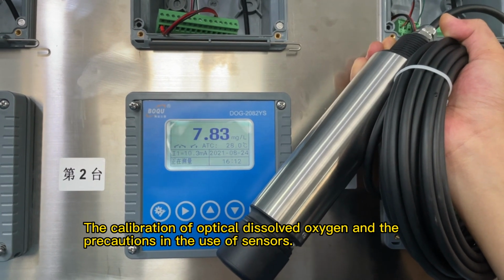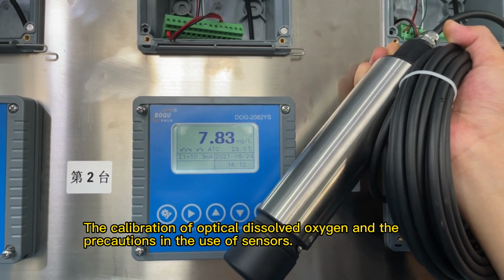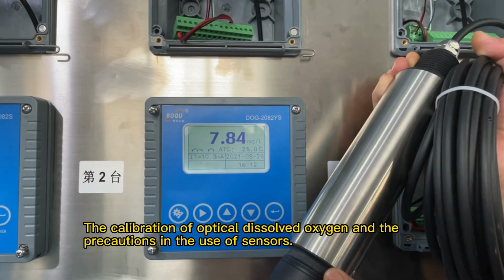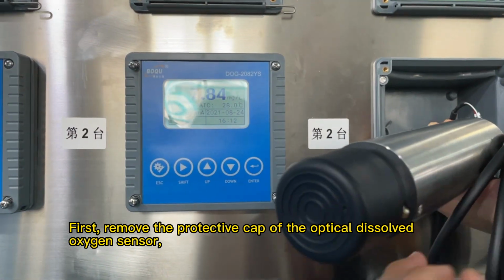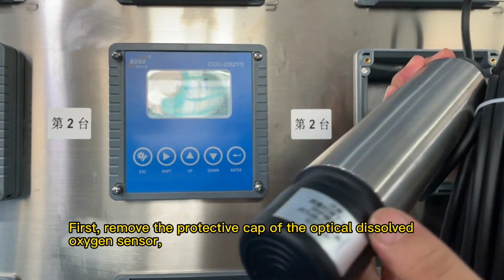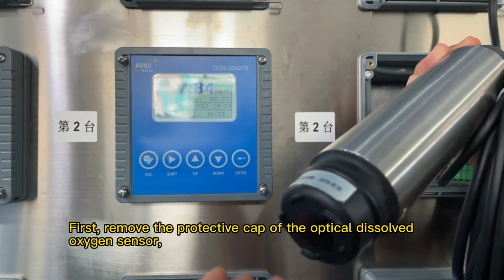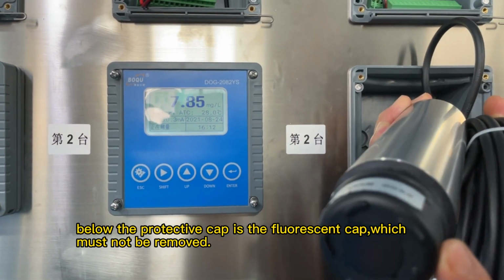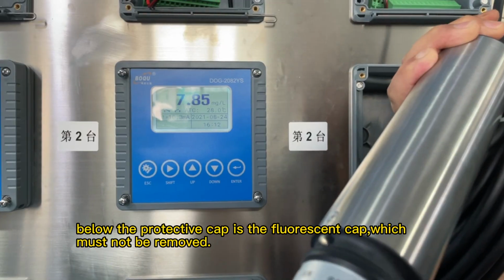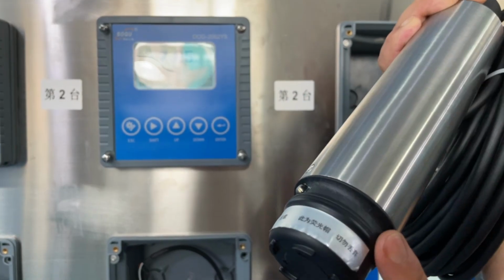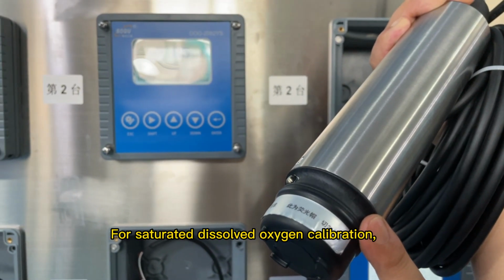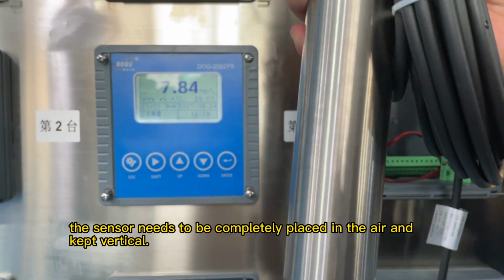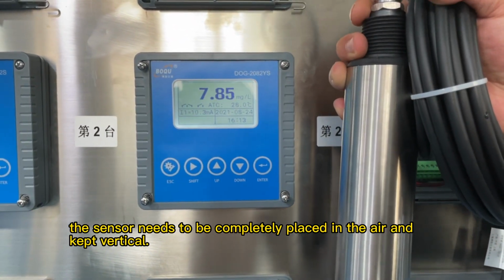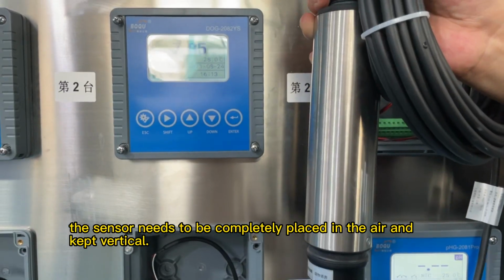The calibration of optical dissolved oxygen and the precautions in the use of sensors. First, remove the protective cap of the optical dissolved oxygen sensor. Below the protective cap is the fluorescent cap, which must not be removed. For saturated dissolved oxygen calibration, the sensor needs to be completely placed in the air and kept vertical.